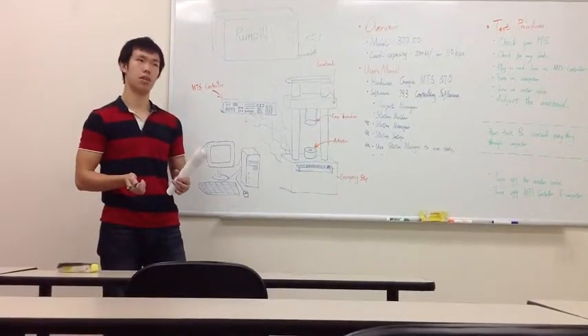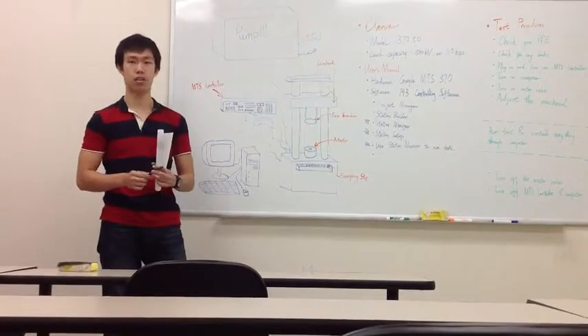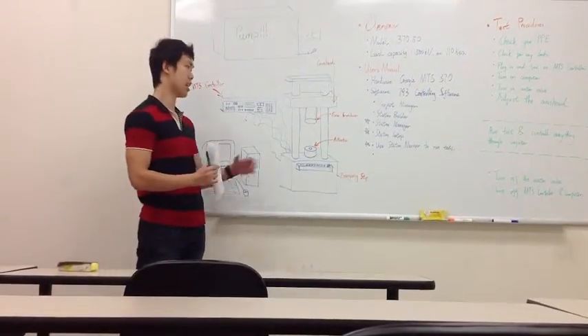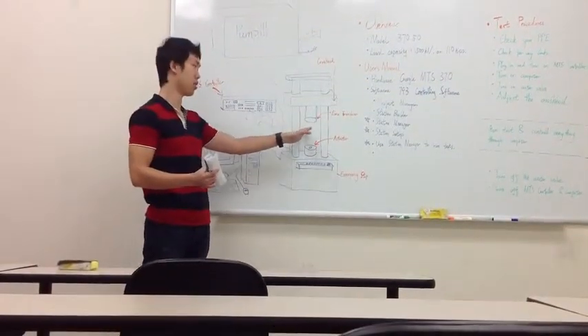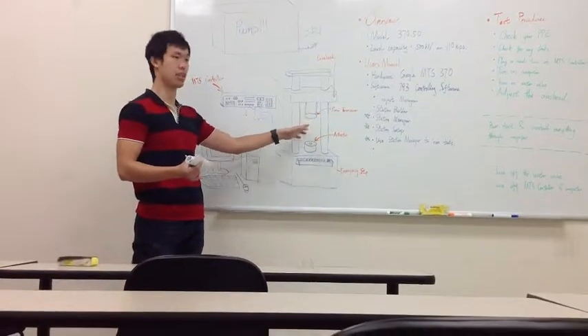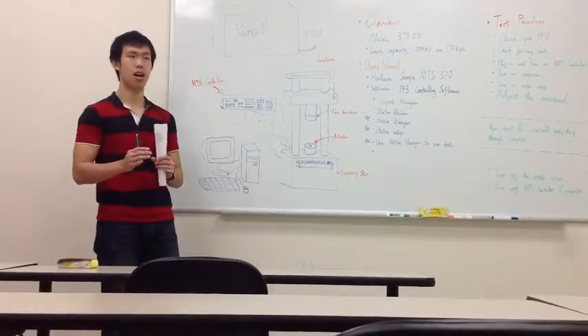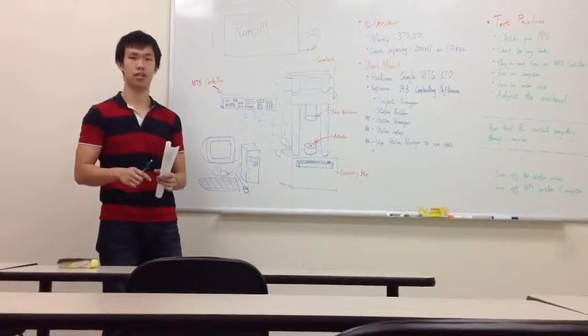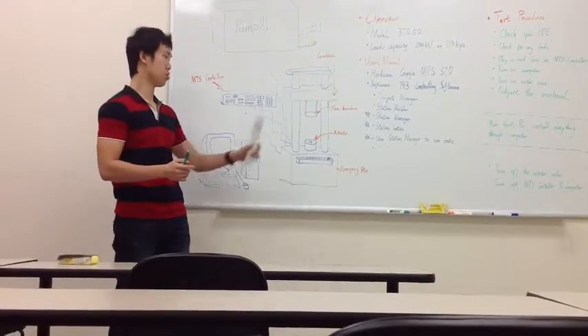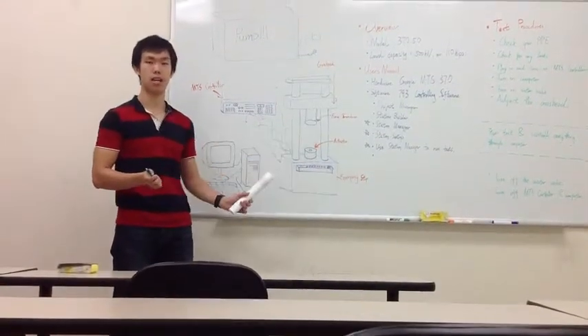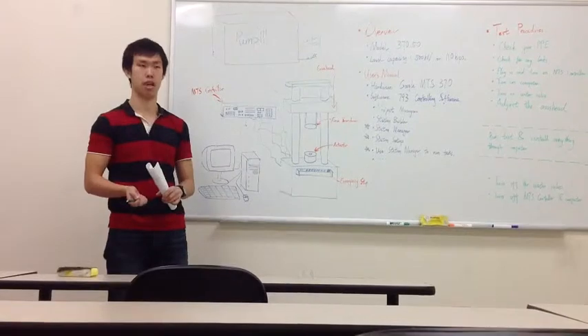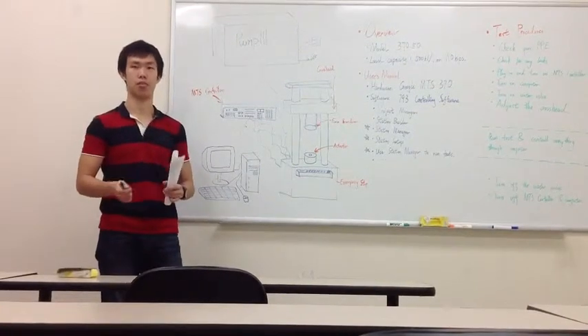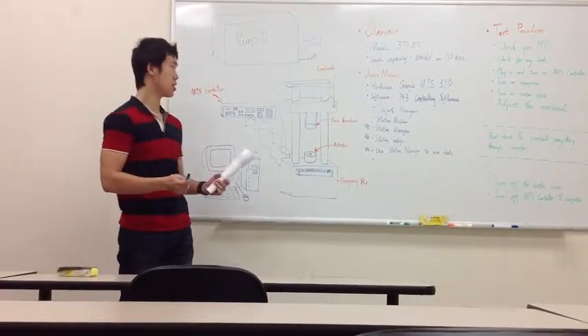But one alternative will be you can attach another piece of load force transducer underneath that with a smaller range of measurement. So you don't use the one that comes with the MTS, but you use the smaller one yourself. So you get more accurate results.